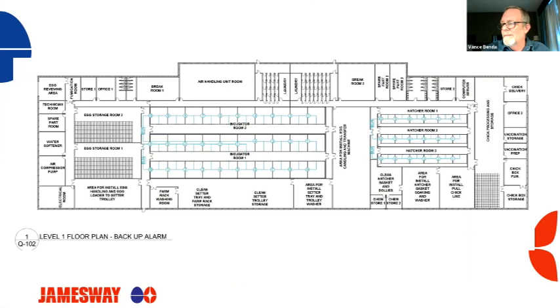Now we'll talk a little bit about this high temp backup alarm wiring. As I mentioned, each one of these boxes can service 16 incubators. So if you were to count, this is 10, and then he's got connected to 6 more. So this box is full, taking care of 16 incubators. This one over here, he picks up these 4 and these 10. So you're going to have a couple empty circuits on that box, which is fine.